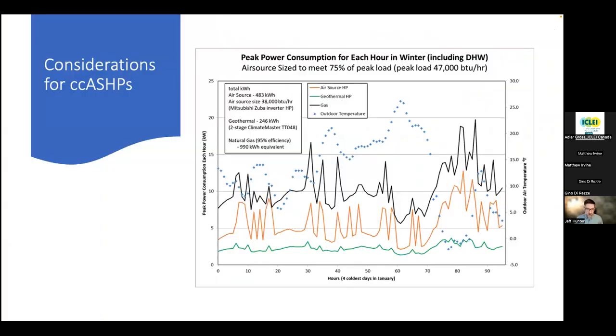How does that tie together when we're looking at comparative between these systems? This chart, I think, does a really good job of putting it all on the same framework. We've got an air source piece of equipment, a cold climate air source heat pump. We've got a gas furnace, and then we've got a typical two-stage ground source heat pump. Now, the ground source is in green at the bottom, lowest energy demand. And what we're looking at here is basically the peak conditions of the year in this particular location. Now, we've got ground source down here, the air source heat pump over here, and then the gas furnace, they've equated again back to kilowatt hours, right? So we've got them on the same plane of how much energy is being consumed here.